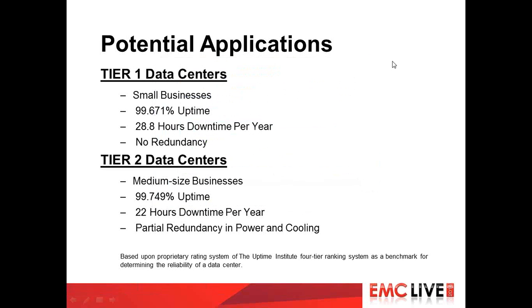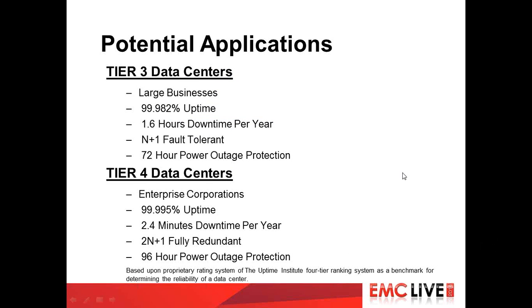Likewise, Tier 2 data centers have a requirement of no more than 22 hours of downtime per year, and again would not be supporting critical infrastructure. But when we get to Tier 3 data centers, with a maximum of 1.6 hours downtime per year, and Tier 4 data centers with a maximum of 2.4 minutes per year—these are the data centers we're finding are very concerned about including HEMP and IEMI protection in the overall scope of protection they're evaluating for disaster recovery and disaster resiliency.